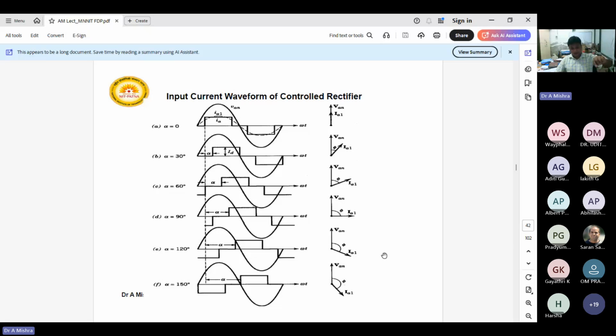So from the same point, my neighbor is also connected. So my neighbor is not getting a good power factor. They are getting voltage and current out of phase. So what will happen? For them, it will be a problem. That is why in some countries there is a penalty, and the penalty is for either disturbing the power factor or injecting harmonics. So harmonics also play an important role.